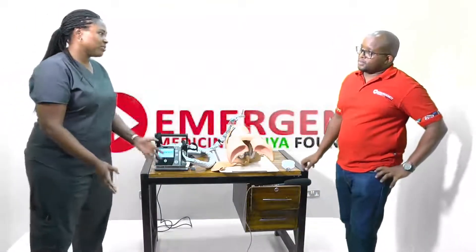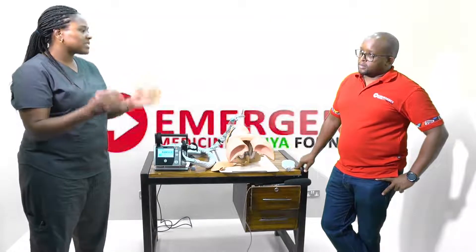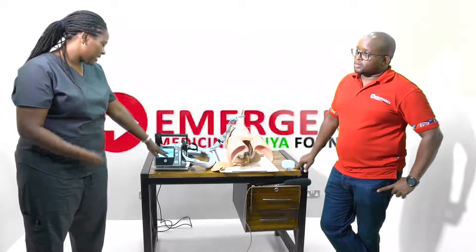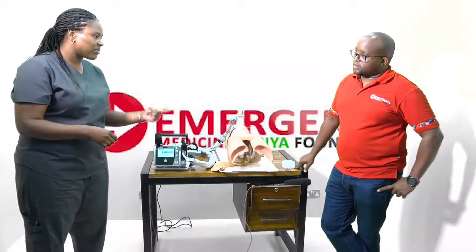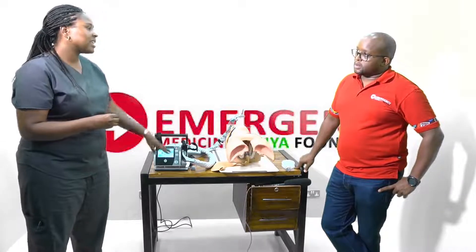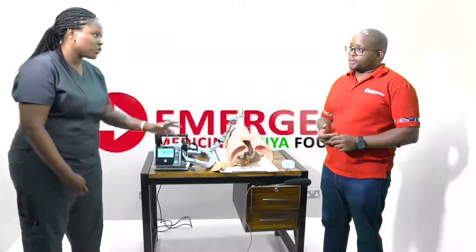ACVC — assist control volume control — is a volume mode. It sets a definite tidal volume and rate. In assist control mode, if the patient initiates or triggers a spontaneous breath, the machine still delivers the mandatory tidal volume. So the machine assists every breath the patient takes, but to a controlled volume. It breathes with the patient, delivering a full set tidal volume whenever the patient triggers.